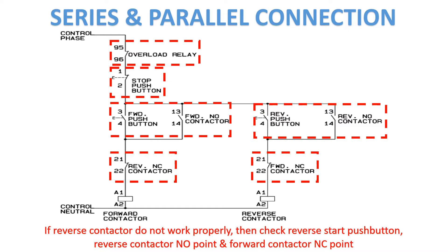If the reverse contactor does not work properly, then check the reverse start push button, reverse contactor NO point, and forward contactor NC point.